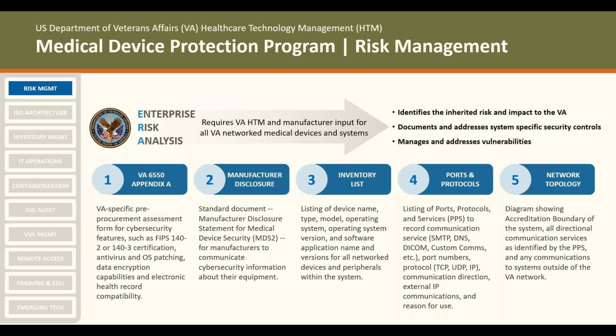Can Biomed apply those patches? Are they required to be applied by the vendor? So, trying to get a full picture: we know that all devices have risk. Now, how can we mitigate those risks? And how is the standard way in the VA that we're going to say, all right, this is how this device is implemented and how these risks are going to be accepted for use. And once that's done, the device has an approved VA enterprise risk assessment.